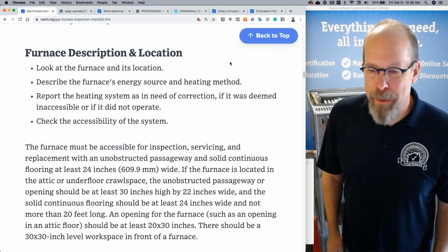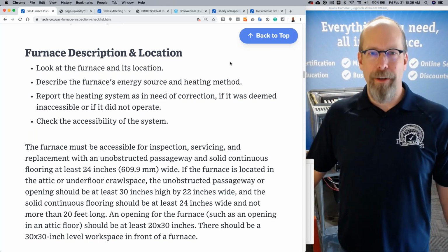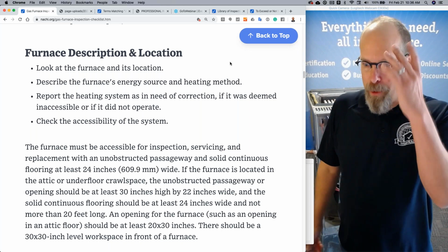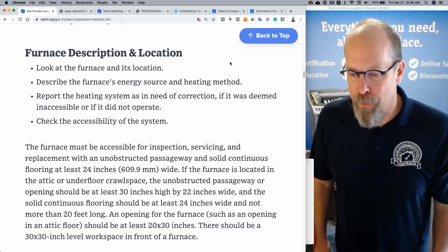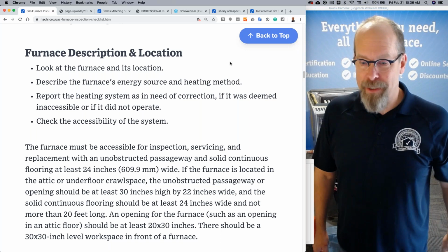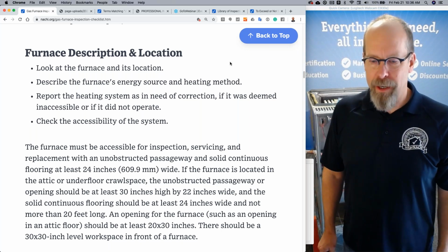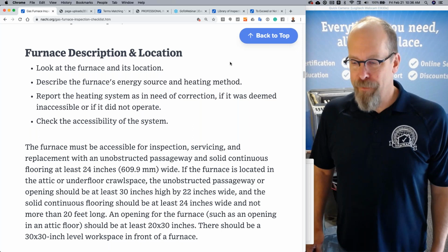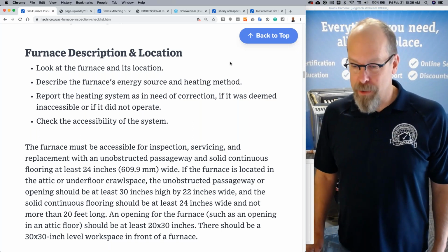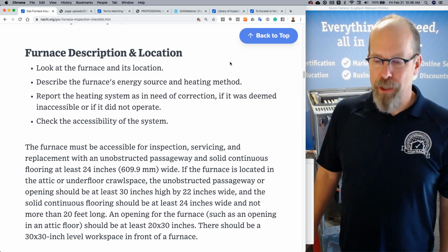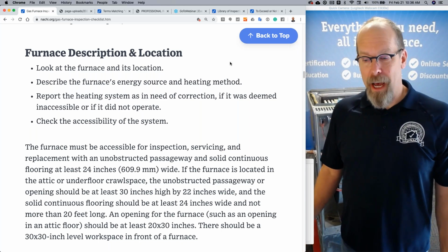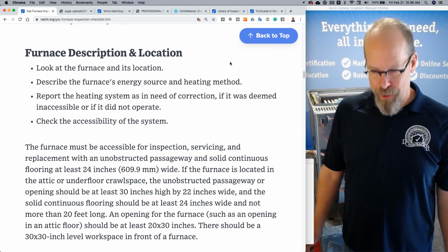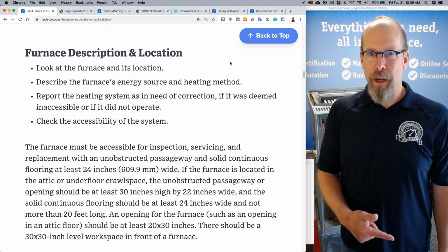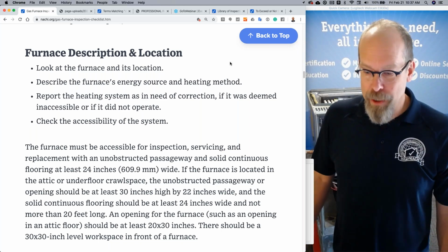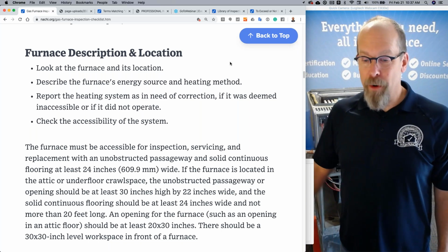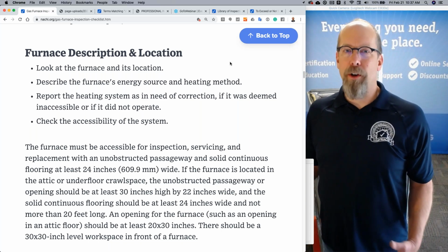But the furnace must be accessible for inspecting, according to code and normal opinion. It has to be accessible for inspecting, servicing, and replacing with an unobstructed passageway and solid flooring at least 24 inches wide. If the furnace is located in the attic or underfloor crawl space, the passageway or opening should be at least, here we go, 30 inches high by 22 inches wide. 22 inches wide. Well, it just said it needed flooring 24 inches wide. And the flooring should be at least 24 inches wide and not more than 20 feet long. Well, so code is all messed up, in my opinion.